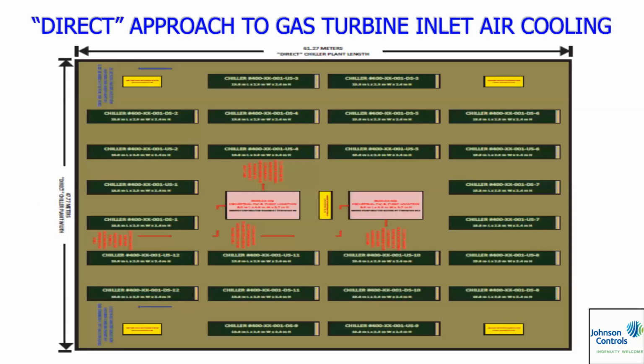Okay, so this is indirect. I'm sorry, this is direct. What you're seeing, those kind of fuzzy, but what you're looking at is basically a football field of air-cooled package chillers. Okay, and you would think, holy cow. Okay, so we got all these package chillers, and typically package chillers, air-cooled chillers. The largest package air-cooled chillers you can get is if it's 50 hertz power is around 400 tons. If it's 60 hertz power, we get up to about 500, 550. That's the maximum. The maximum voltage is 400 volts, 50 hertz, or 460 volts, 60 hertz.